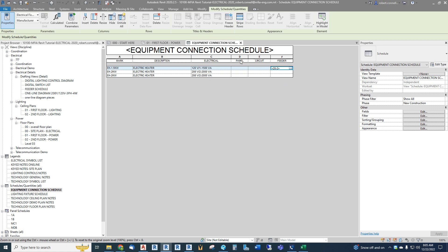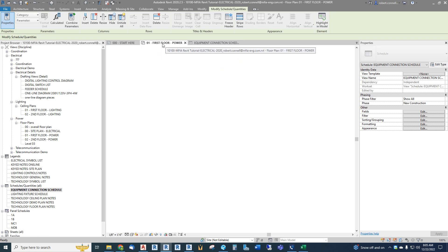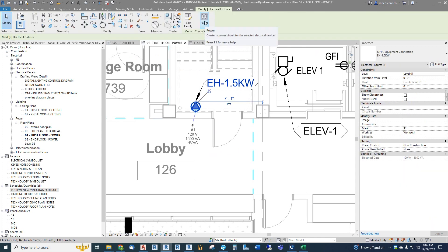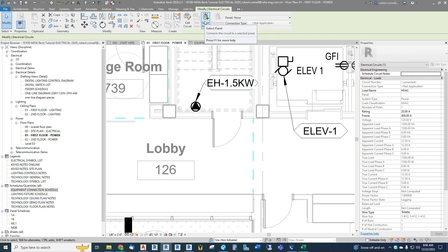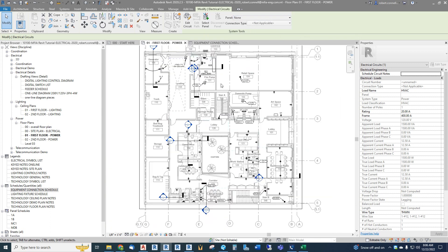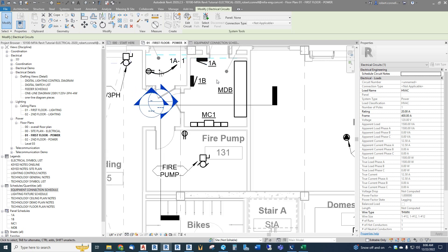Now we're going to work on filling in the panel and circuit information. We can't do it in the schedule — we do it back on the plan, like we did with receptacles. Click on the heater and use the power button to get to the circuiting. Now we have our choice of selecting a panel visually by clicking on it or using the drop-down. In this instance, our design decision is to use panel 1B for mechanical equipment.